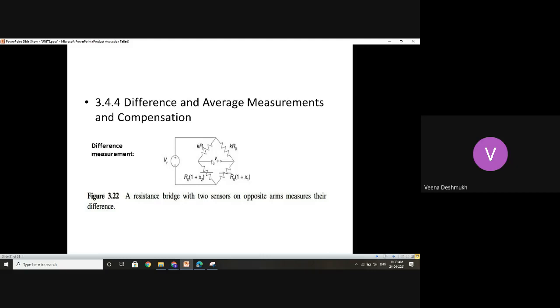So for every step, say the temperature varies up to 1000 degrees centigrade, if you are monitoring using PT100, and if your power supply is say 5 volts, then over the 0 to 5 volts range, the temperature measurements of say 100 to 1000 degrees centigrade. What is the range over there? It is around 900 degrees centigrade. So these 900 degrees centigrade have to be accommodated in 0 to 5 volts variations.